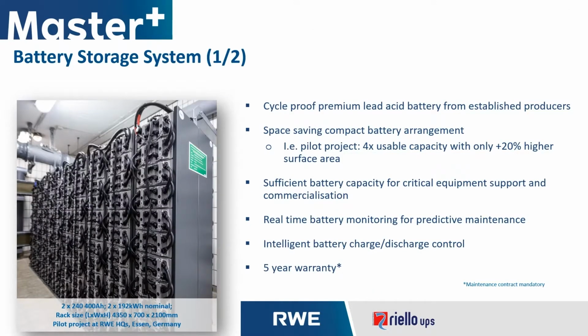As with all UPS solutions, the battery storage system is critical. For this particular project, we specifically chose cycle-proof premium lead-acid batteries from a well-established producer. This, in conjunction with a compact battery arrangement, enabled the system to provide up to 4 times usable capacity, but with only a 20% increase in the surface area requirement. The primary purpose of the battery was obviously to provide sufficient battery capacity for the critical equipment support along with the commercialization aspects of the project.